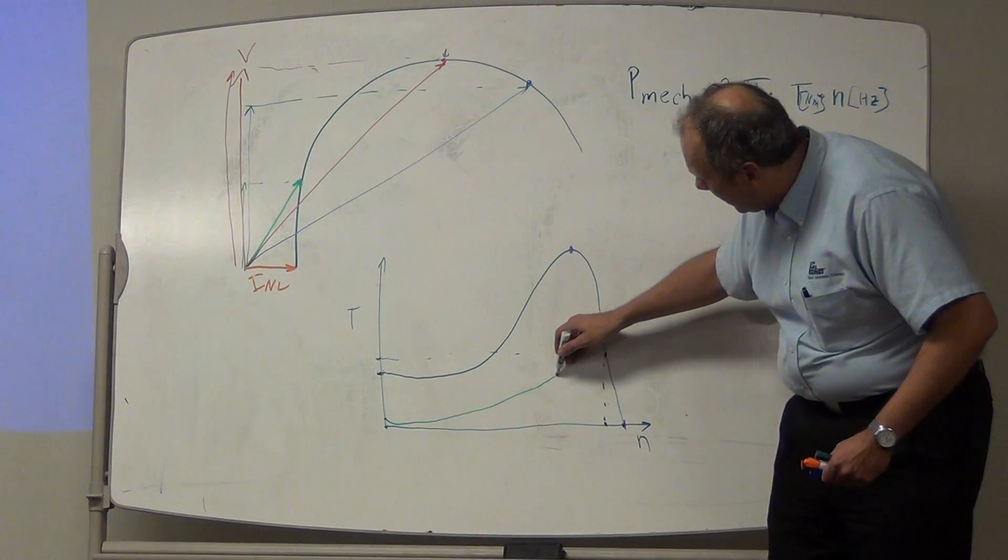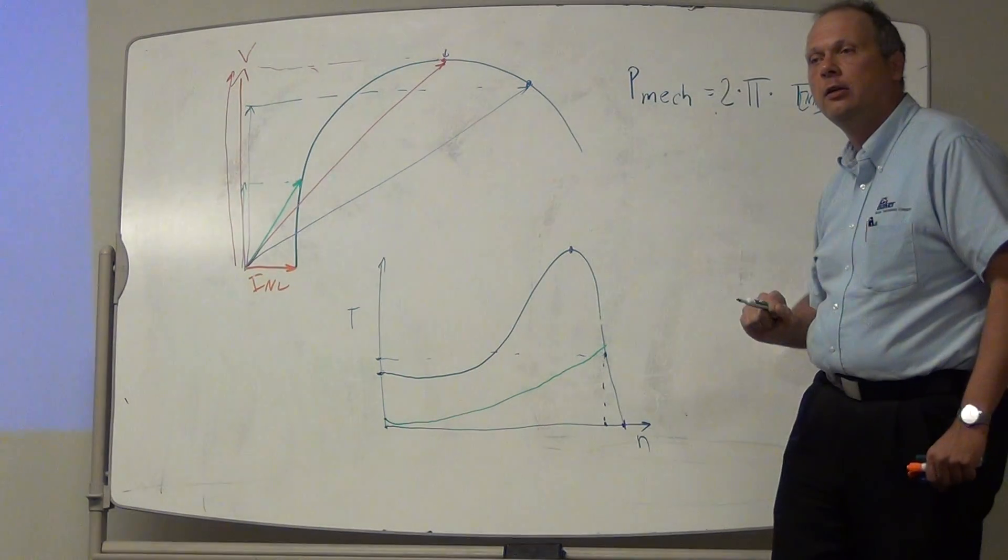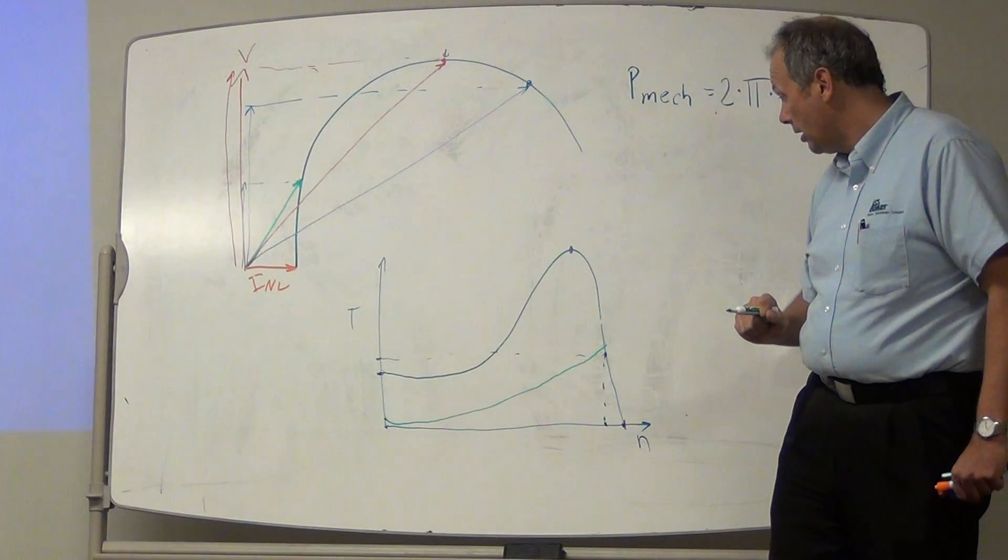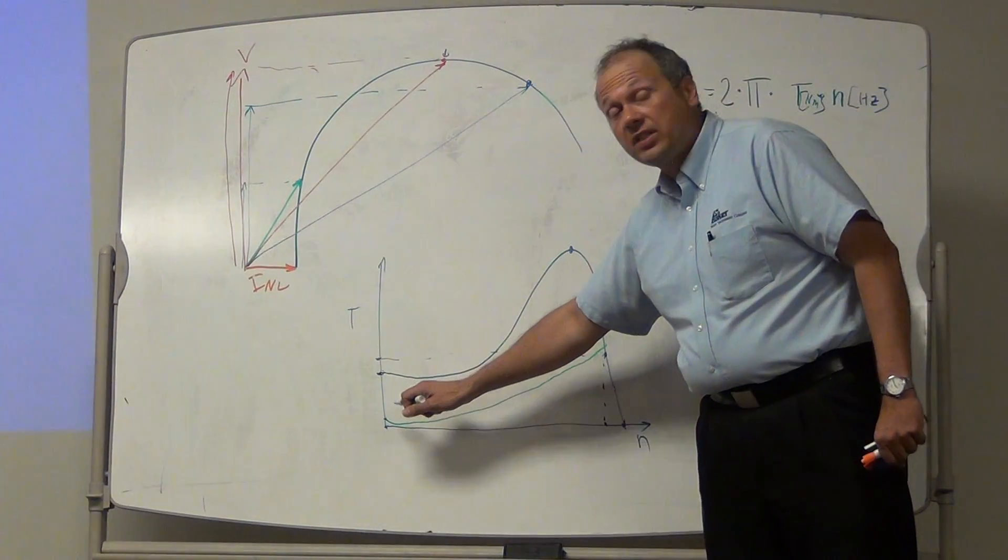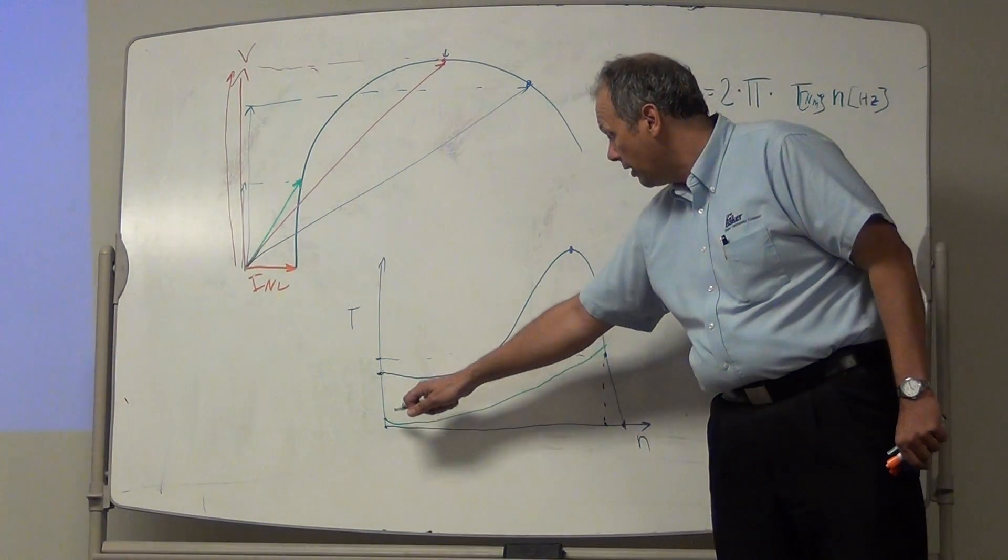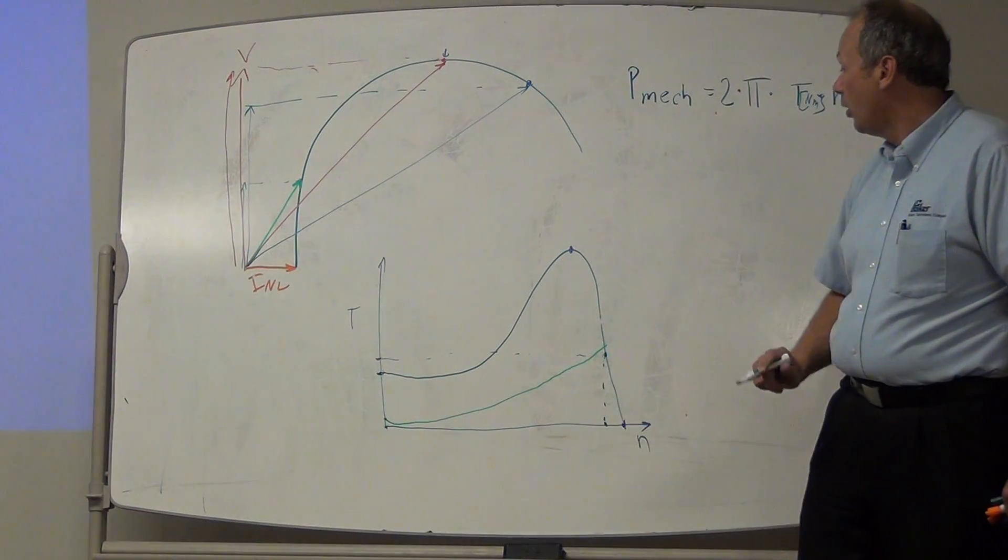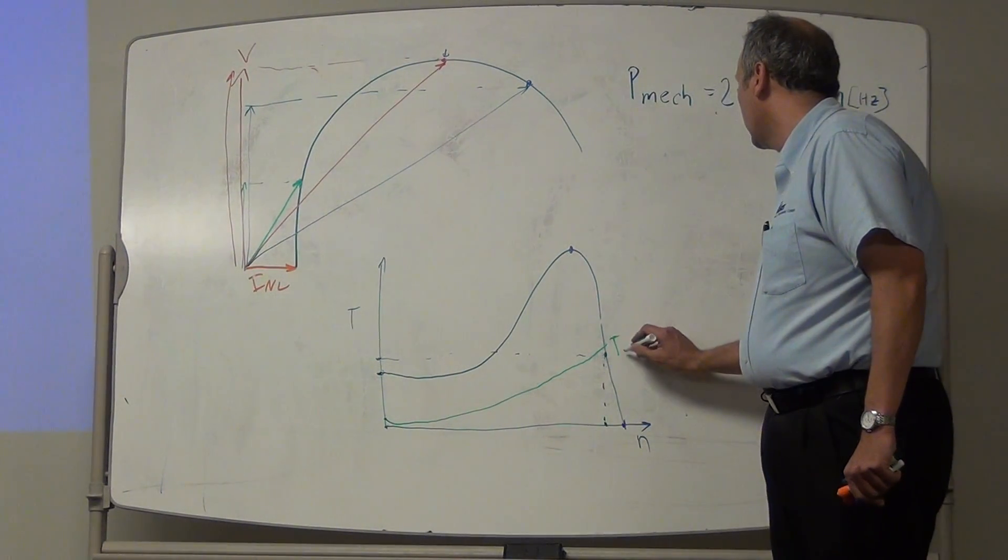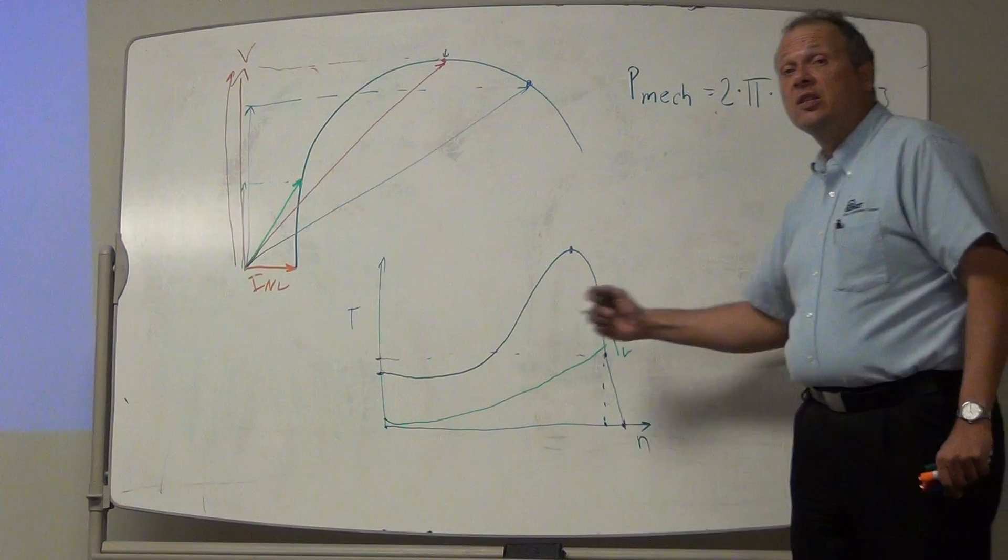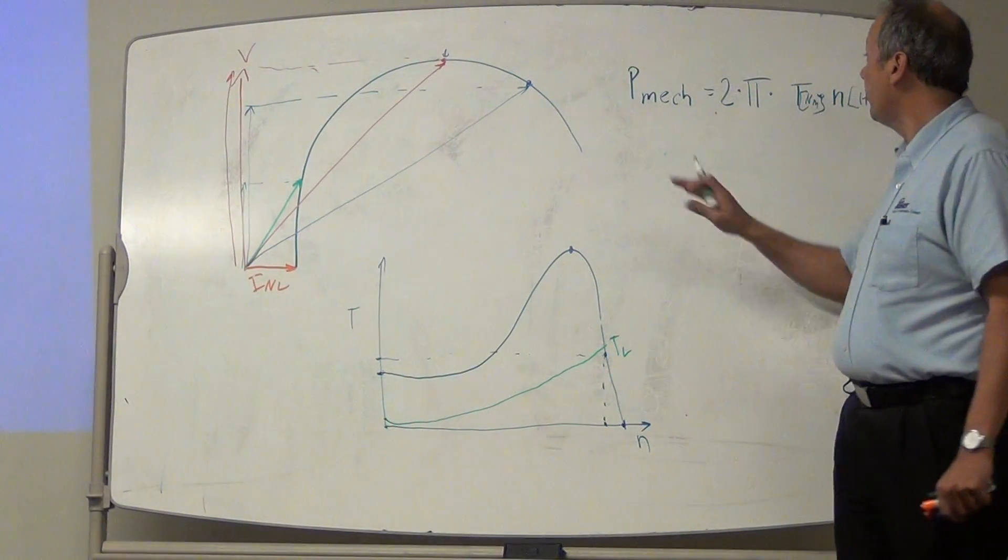And then I have some kind of a parabola-looking curve. So for centrifugal loads, this here, the torque goes up. This is my load torque, TL. It goes up with a square of speed. What does it mean for my power? That goes up with a square of speed. Then I multiply it with speed.